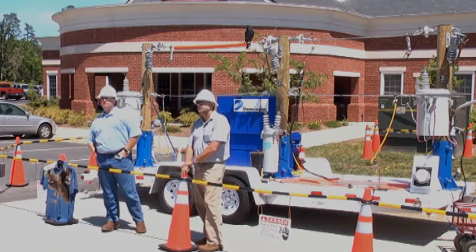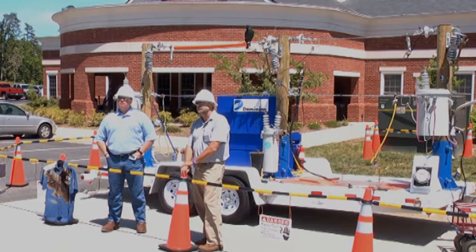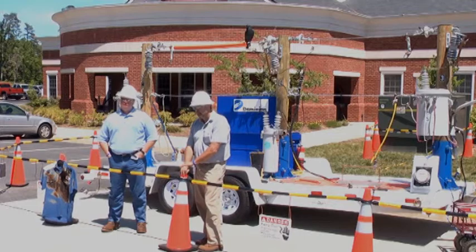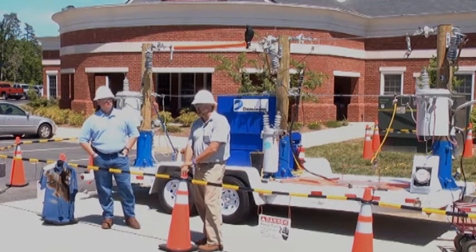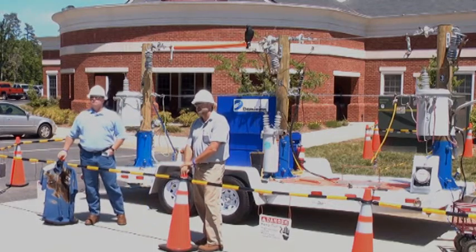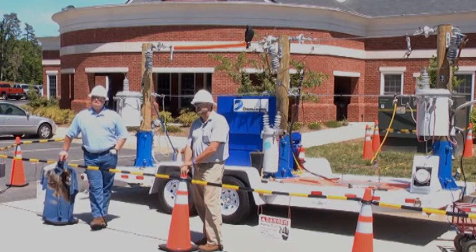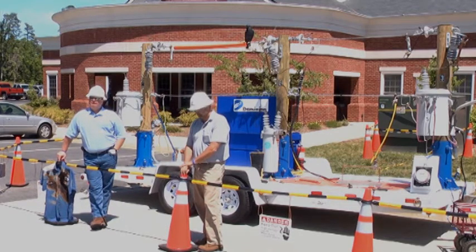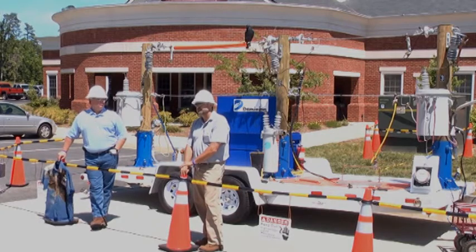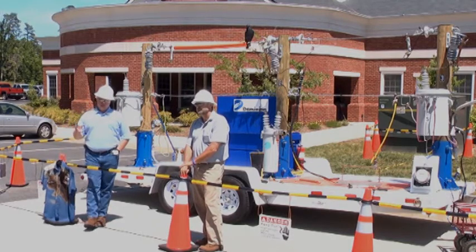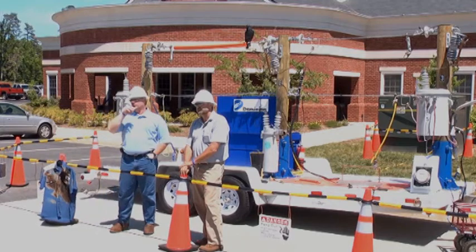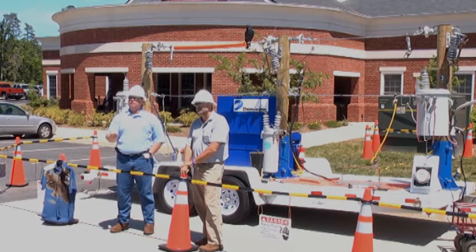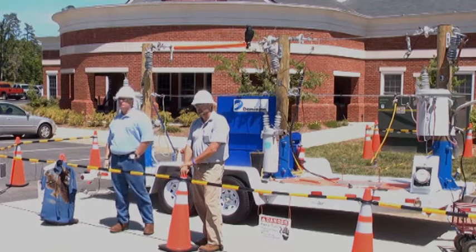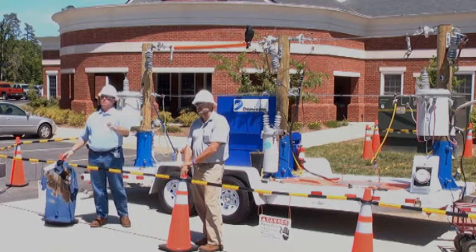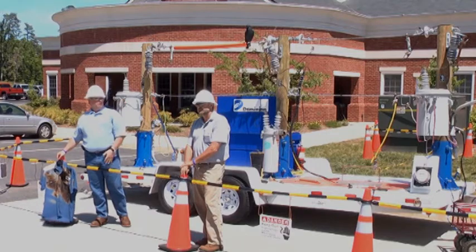How common is it in storm conditions that your power lines energize other cables, like telephone cables? During a major event, it's very common. So would it be wise to assume that when we come up on telephone cables on the ground that they could be energized? Yes, that's the best assumption. In fact, we have a rule that our guys won't get on any what we call foreign conductors other than ours, whether it's cable TV or telephone, without rubber gloves and sleeves. Because we assume it's up on an energized pole.